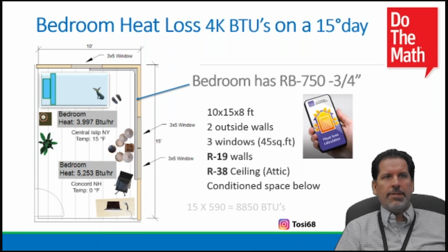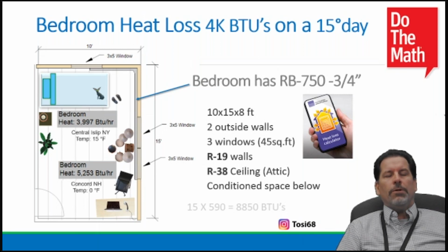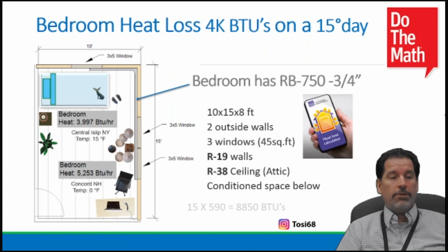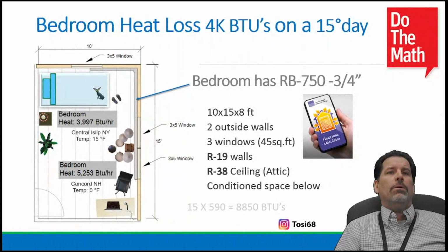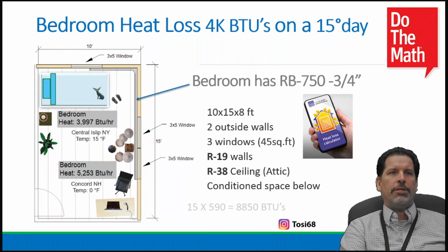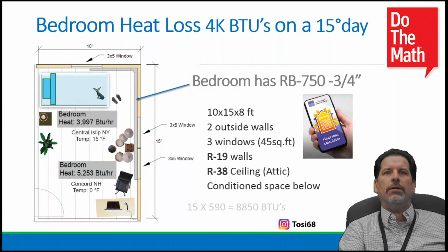Now, I'll say this because that question kind of stems something: lowering water temperature does have a plateau for certain pieces of equipment, meaning cast iron. Cast iron is not a condensing piece of equipment. Can we make it condense? Absolutely. But do we want it? No - we will kill it, shorten its life, and we want to maintain the longevity we know cast iron for. So 140 is that flat line, the lowest I'd say you ever want to go. We'll talk more about lowering water temperature to condense, and that's going to be something a little less than 140.